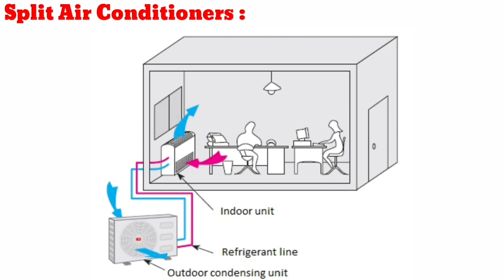The indoor cabinet also typically includes a furnace or the inside part of a heat pump. The indoor and outdoor units are connected by a refrigerant line. The design is a DX direct expansion vapor compression cycle and the heat rejection is via air cooled condenser. Compared to window air conditioners, split units make less noise since the noise-generating component — the compressor — is usually in the outdoor cabinet.